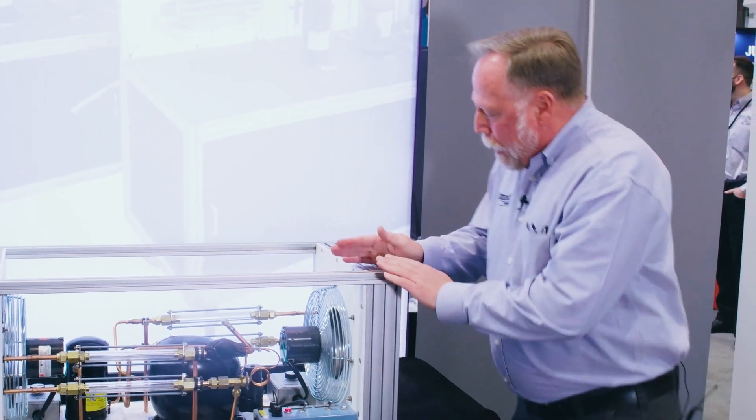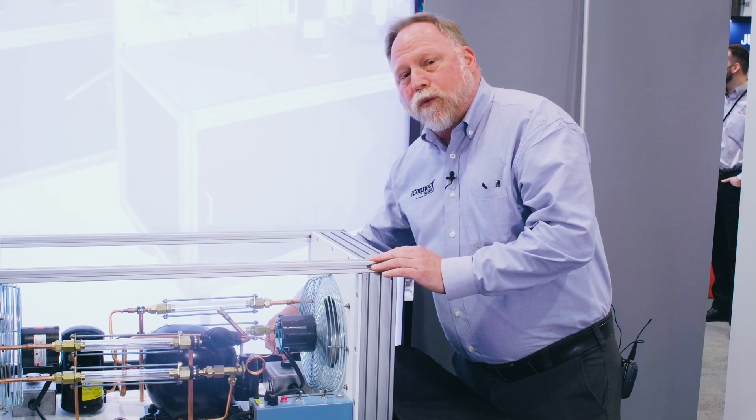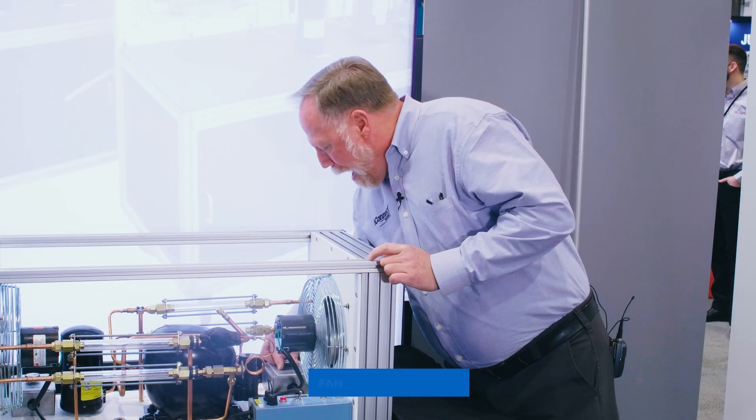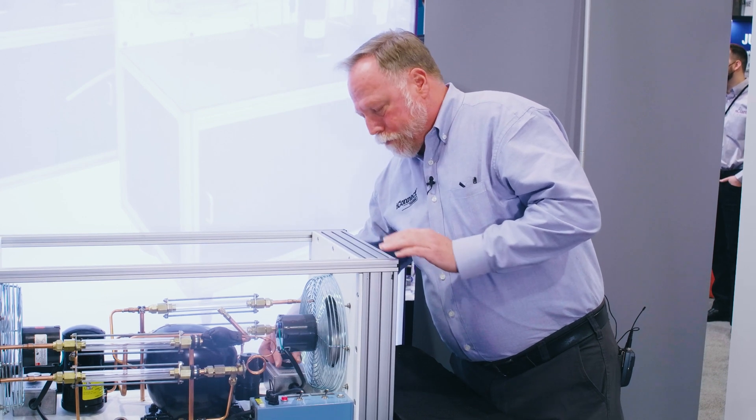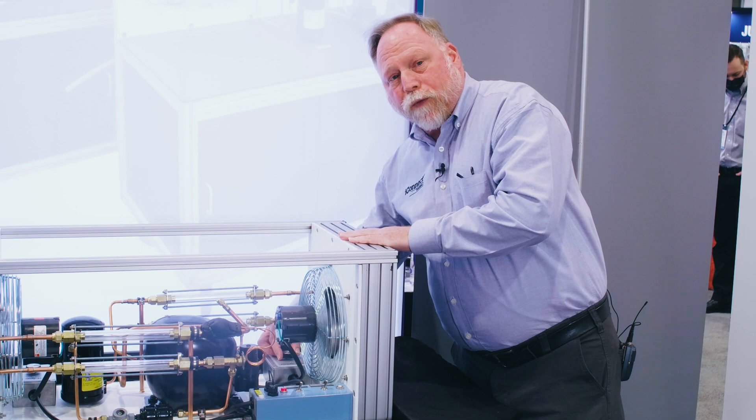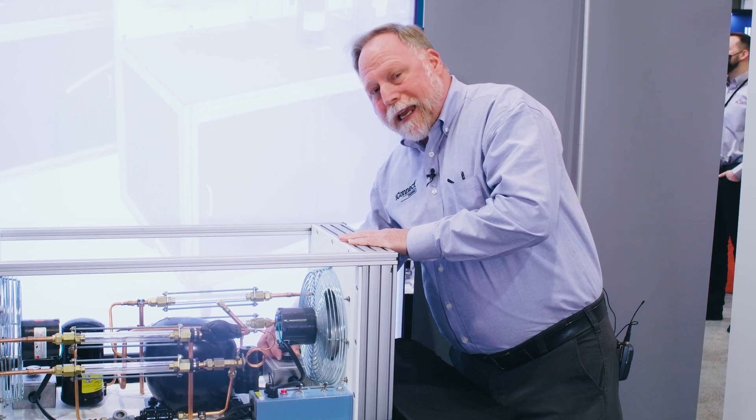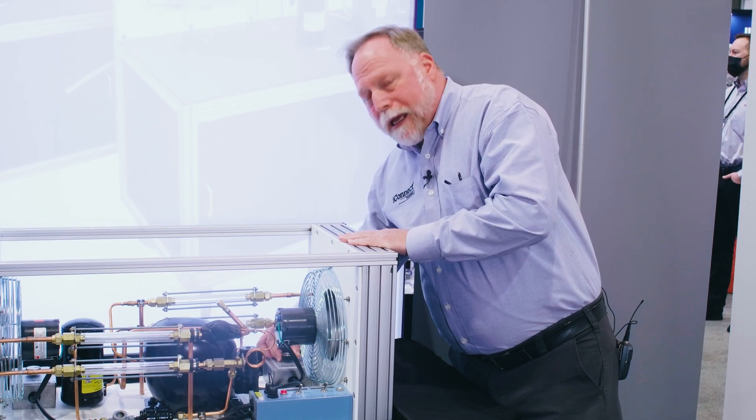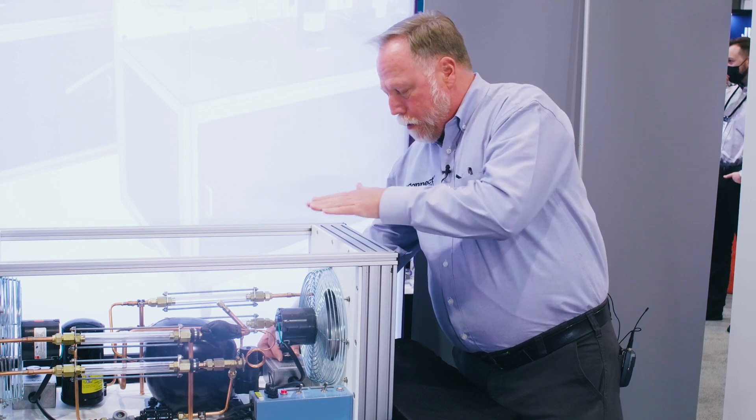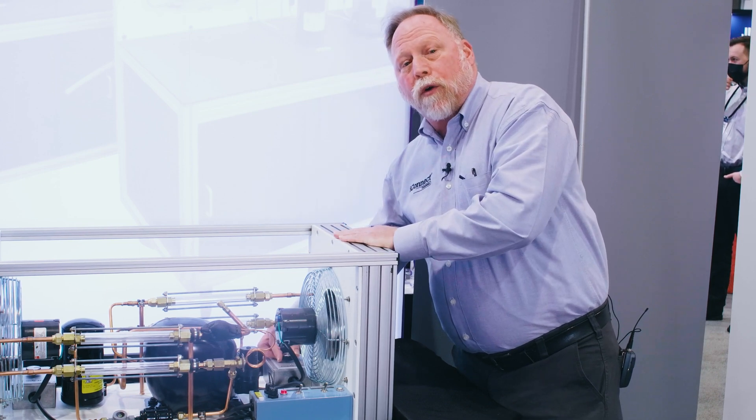The other thing I like to point out is that back here by the fans, we have a controller that actually controls the fan speeds. So I can actually slow it down. And that's going to affect our refrigerant flow. And then I can even dial it all the way down, I can even turn it completely off and show what happens when we lose airflow across the coil.